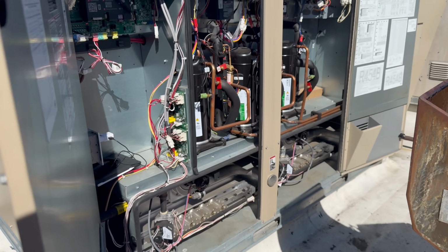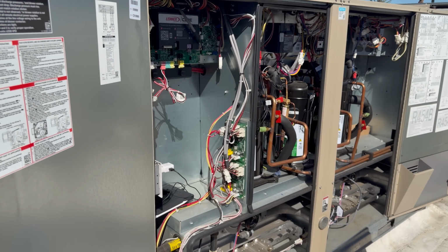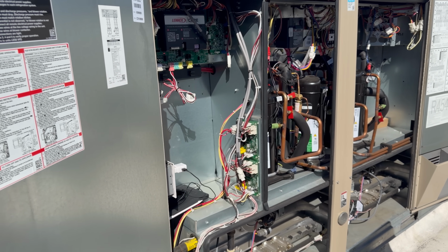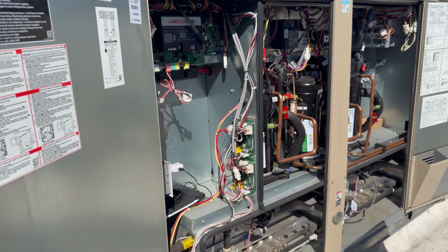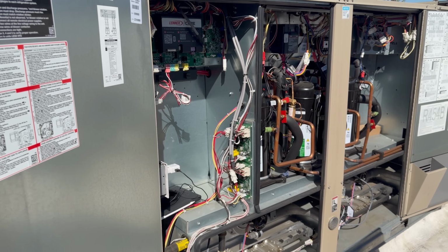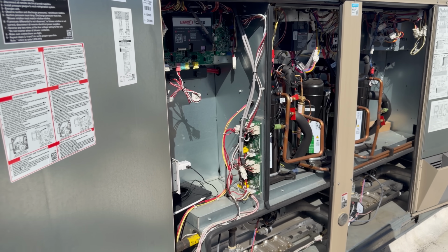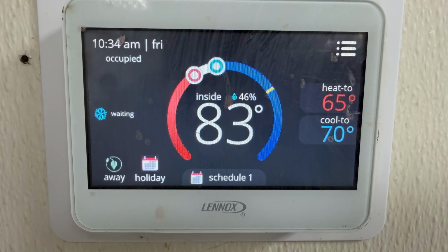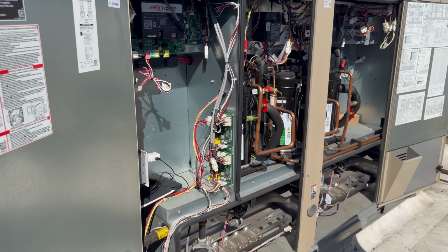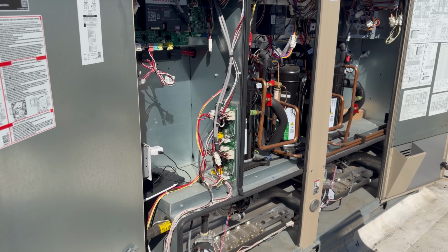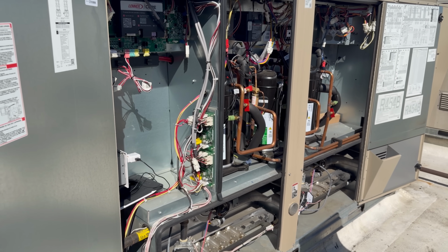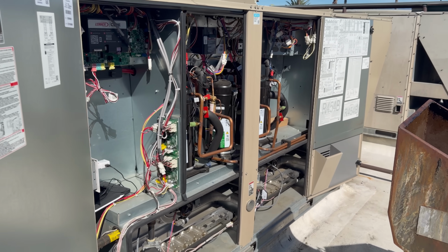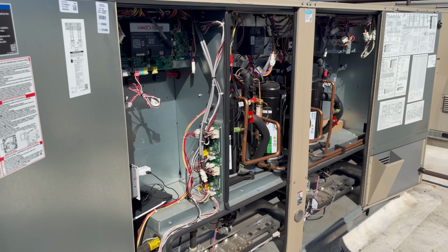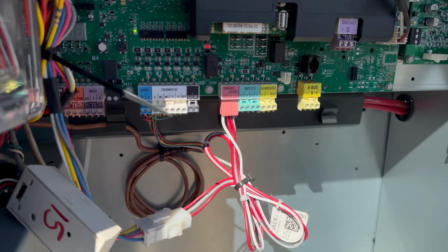That baffles me. So someone took the entire zone sensor off. It looks like they changed some ceiling tiles and someone just ripped it out and didn't bother letting us know. Apparently they got all the ceiling tiles replaced like 5 days ago, so they've been going without a kitchen AC for over 5 days. Here's your sign, I guess. So we're gonna profile the unit and check everything else out to make sure it's nothing more than just a zone sensor.